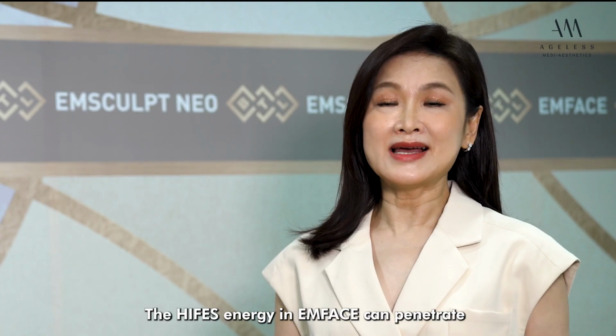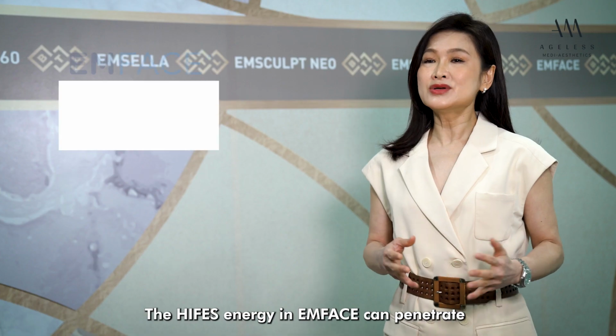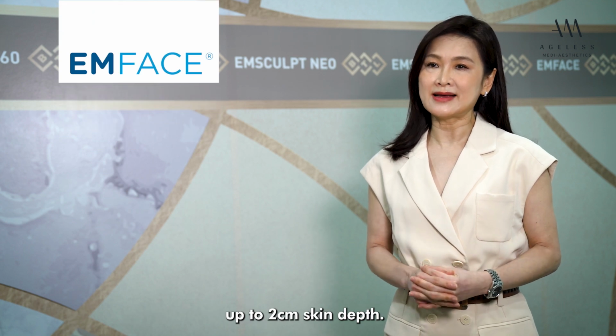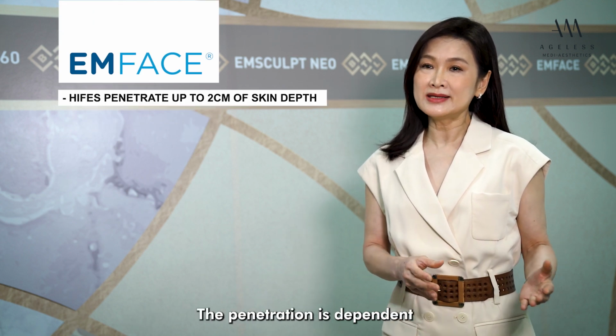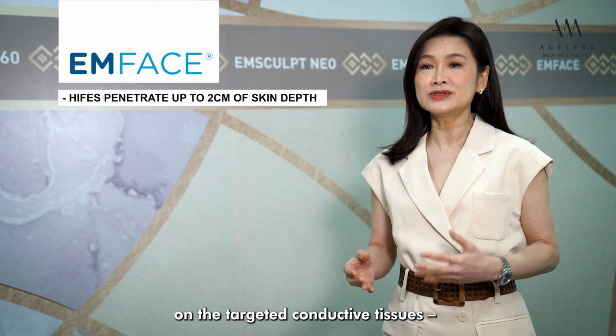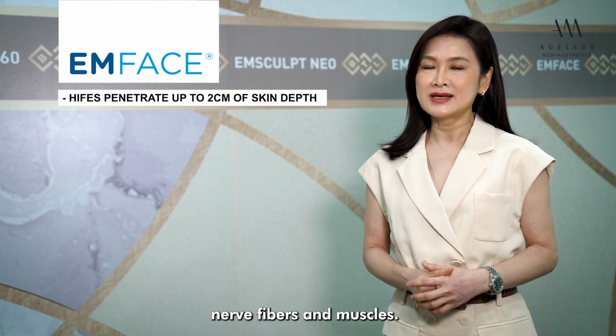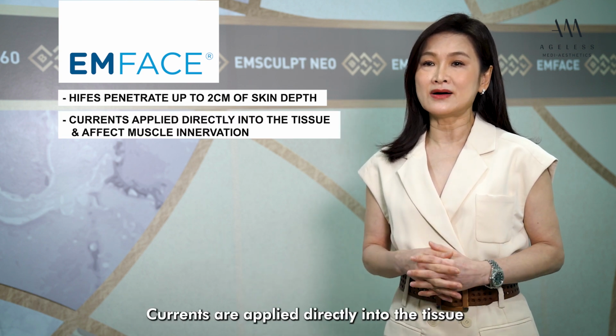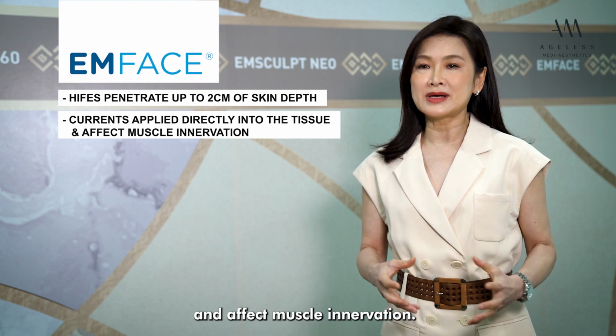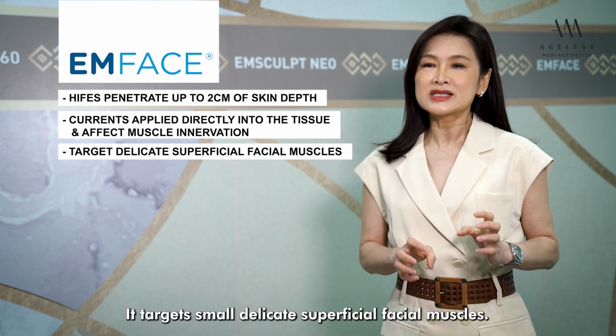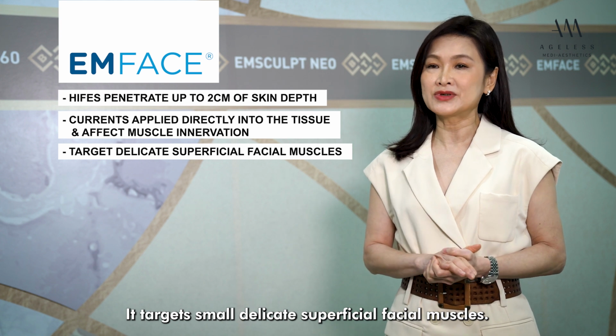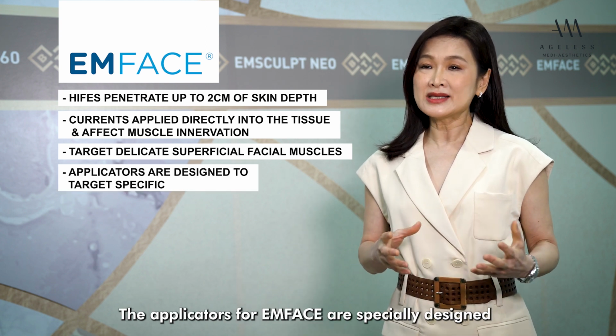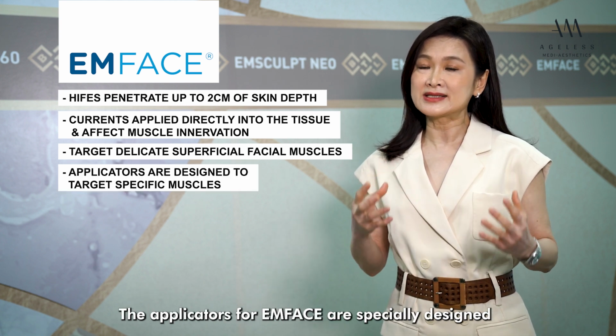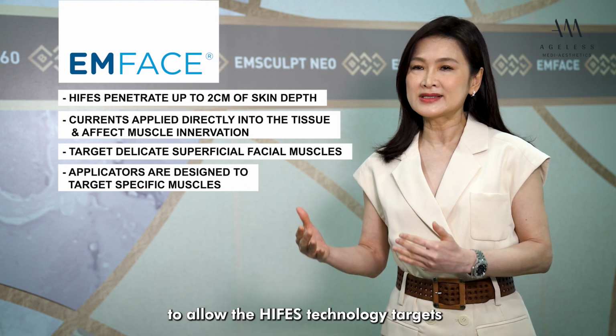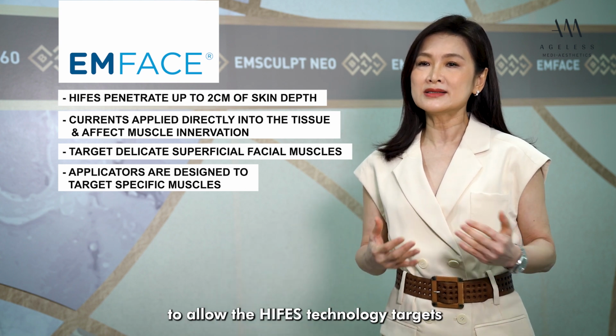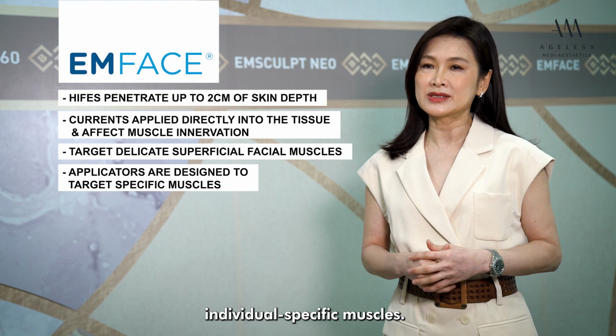Now, the HIFES energy in Emface can penetrate up to 2 centimeters skin depth. The penetration is dependent on the targeted conductive tissues, the nerve fibers, and the muscles. Currents are applied directly onto the tissue and affect muscle innervation. It targets small, delicate, superficial facial muscles. The applicators for Emface are specifically designed to allow the HIFES technology to target individual specific muscles.